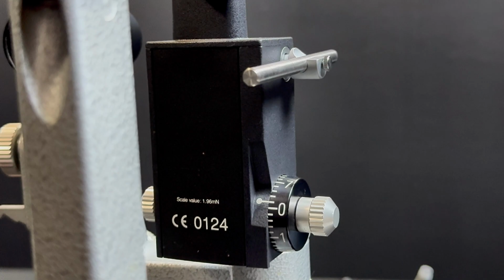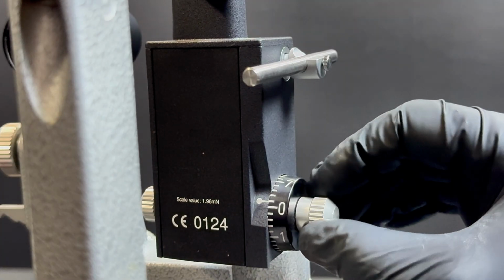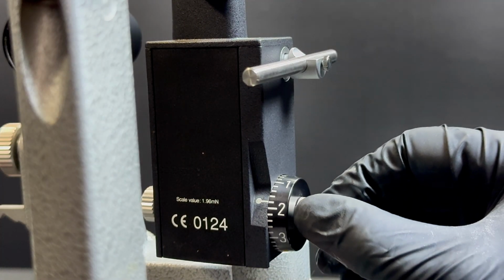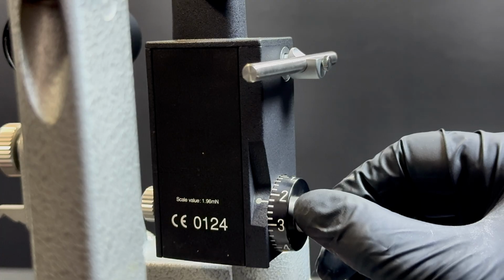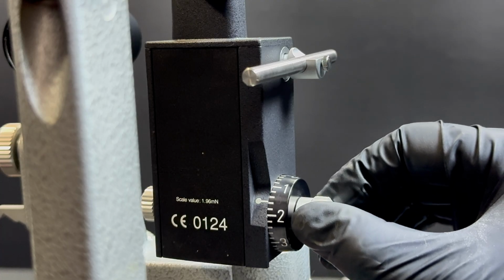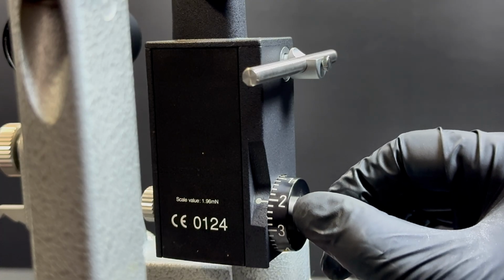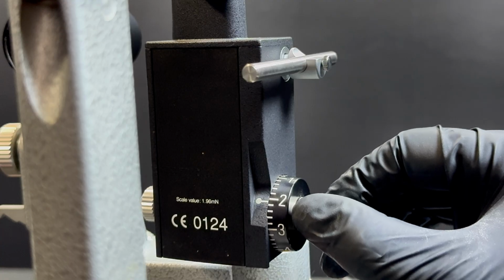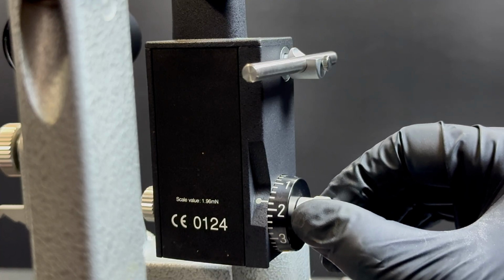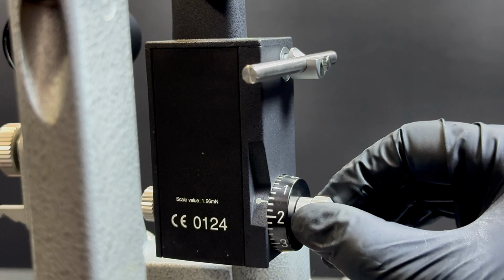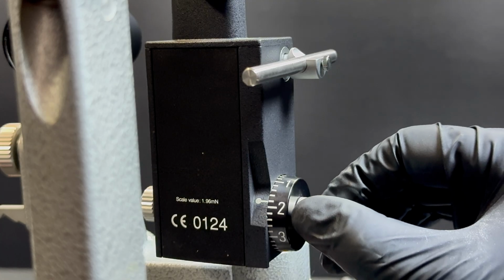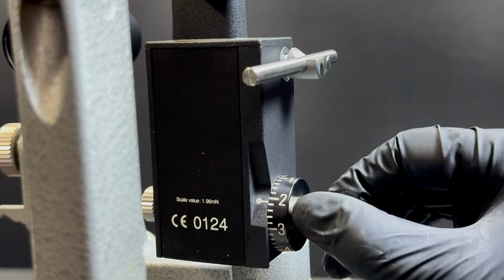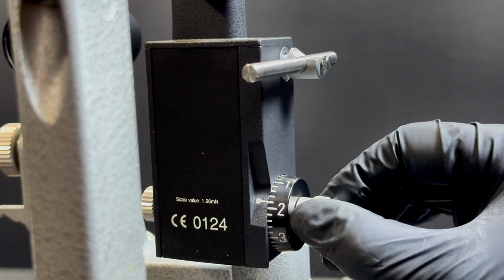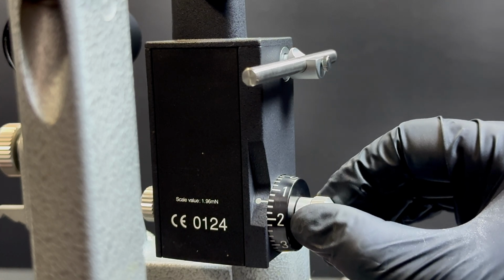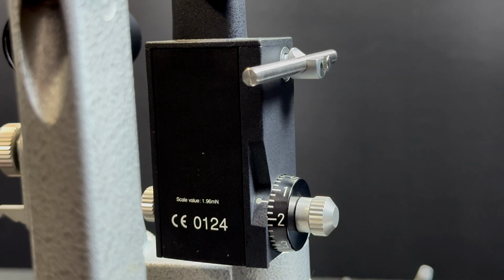For our final example, we're showing a tonometer that is out of calibration and exhibiting a sticking condition. The feeler arm responds on either side of 2, but not at the correct points. Instead of returning near 1.95, it drops early at approximately 1.6. It also drops late at approximately 2.2, beyond the expected position. This behavior indicates the tonometer is out of calibration and requires service.